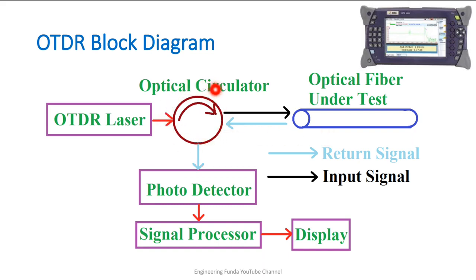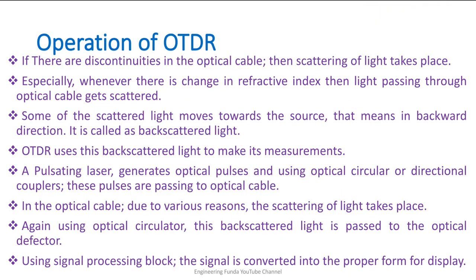The circulator circulates the signal in a clockwise direction, so the input goes into the fiber and the reflected signal comes back to the photo detector. The detected signal is given to a signal processor and on the display we observe the position of the fault and what category of fault is happening. If there are discontinuities in the optical cable, scattering of light takes place, especially whenever there is a change in refractive index, and some of the scattered light moves backward toward the source.